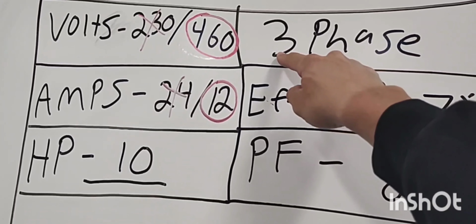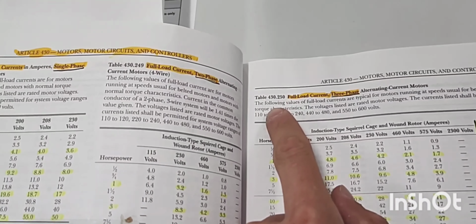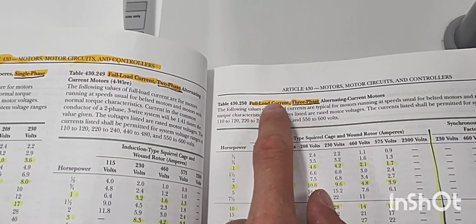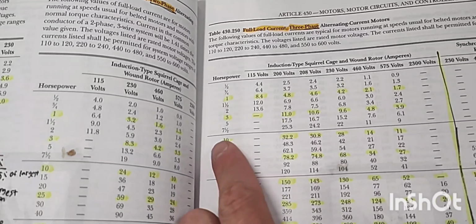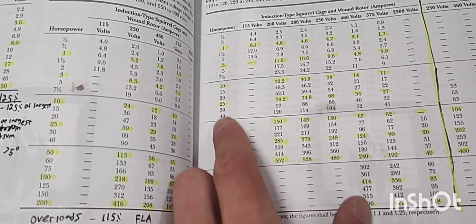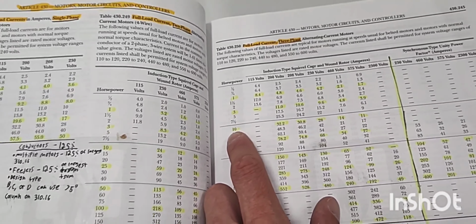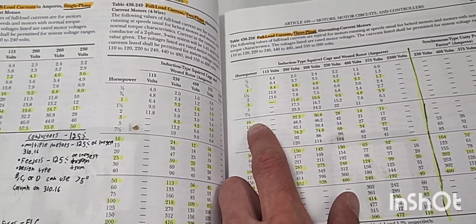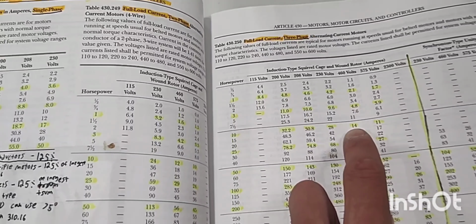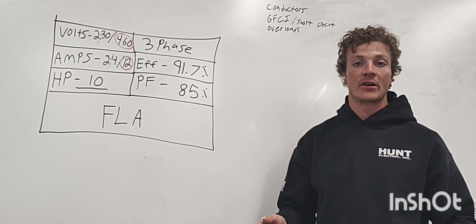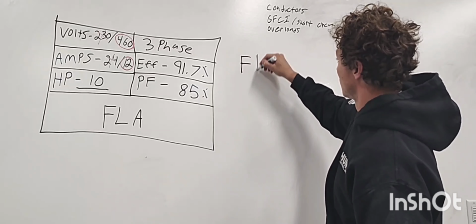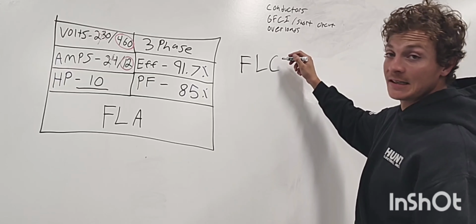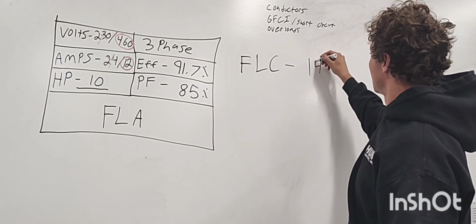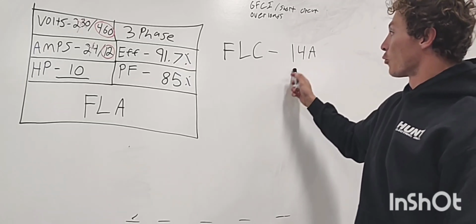So if you'll look right here, it's 3-phase. Let's come into our code book. 430.250, full load current, the FLC, 3-phase. Now it was 10 horsepower, and I believe the voltage was 460. So 14 amps, found in our NEC. The full load current in the NEC, the code book, it was 14 amps. Okay, so we have 14 amps.